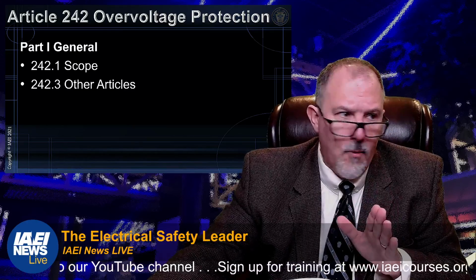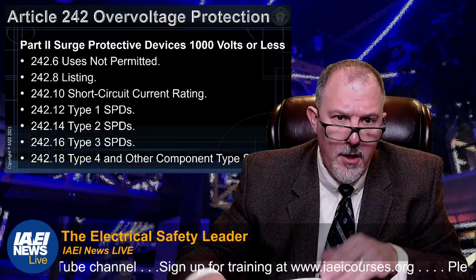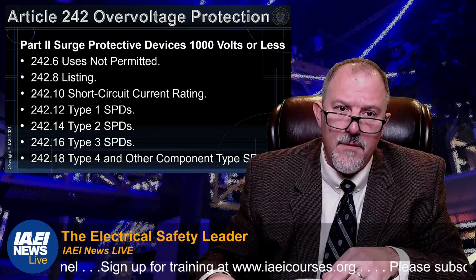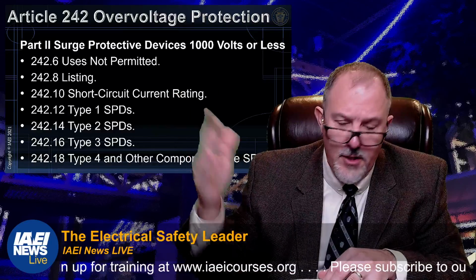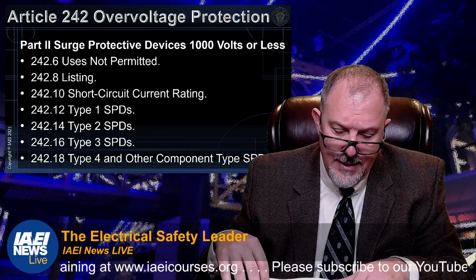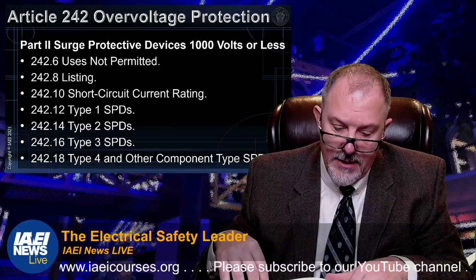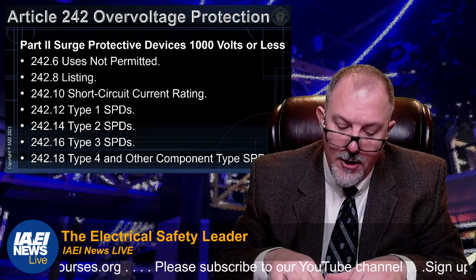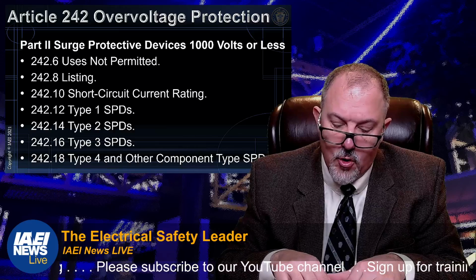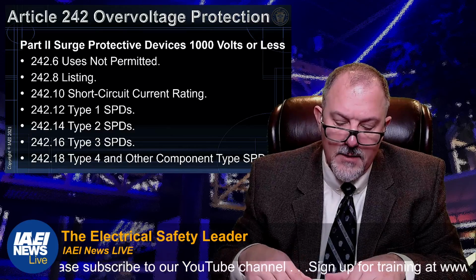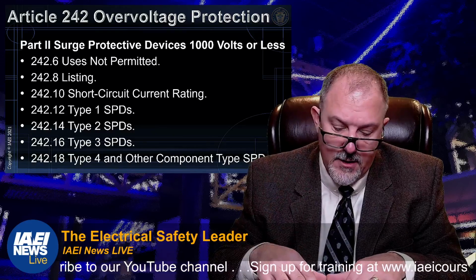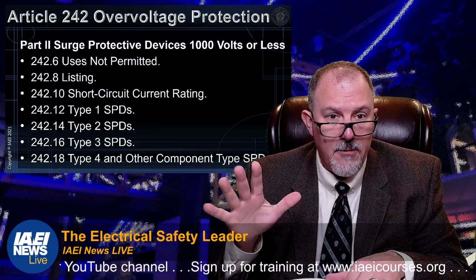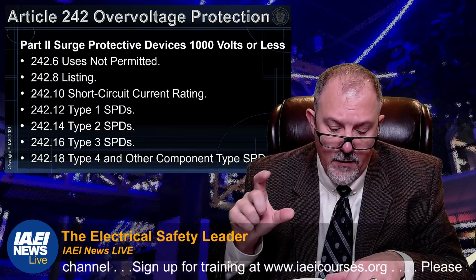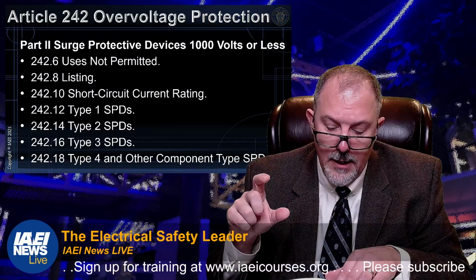So that's Part 1. Part 2 are surge protective devices, 1,000 volts or less. You have where you're not permitted to use those, 242.6. These are on ungrounded systems, impedance grounded systems, or corner grounded delta systems, unless specifically for use on those systems. Again, voltage is a consideration in properly applying these surge protective devices.